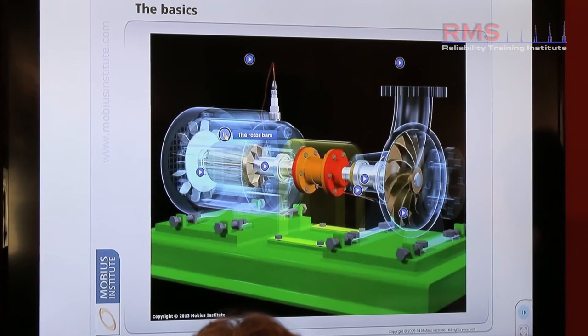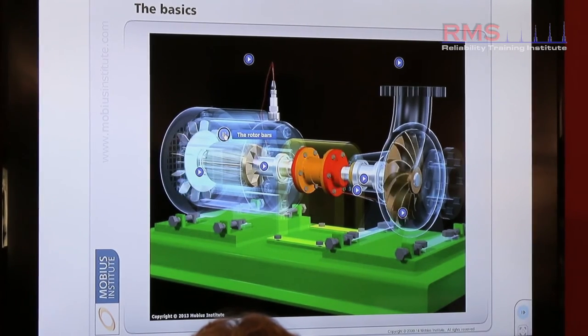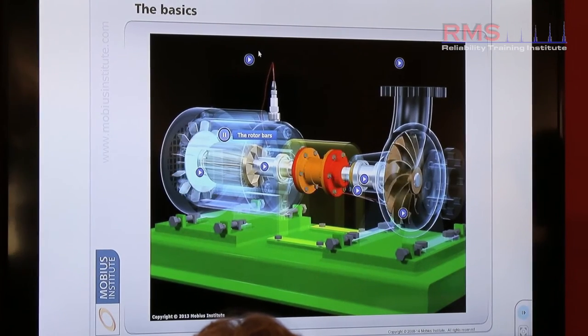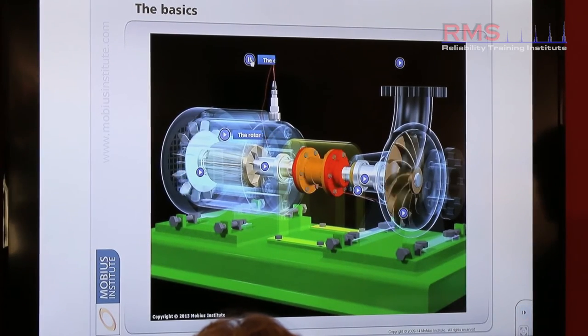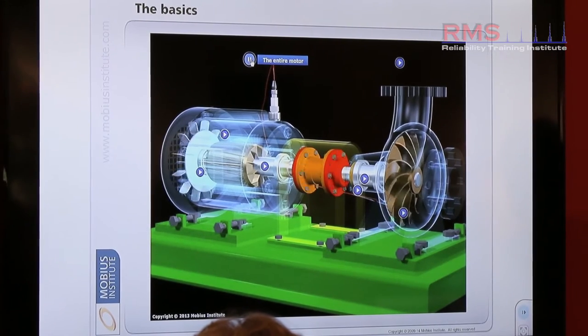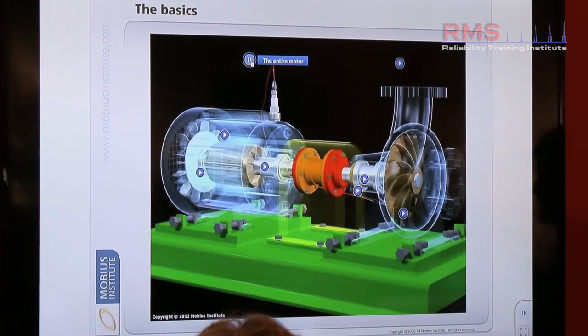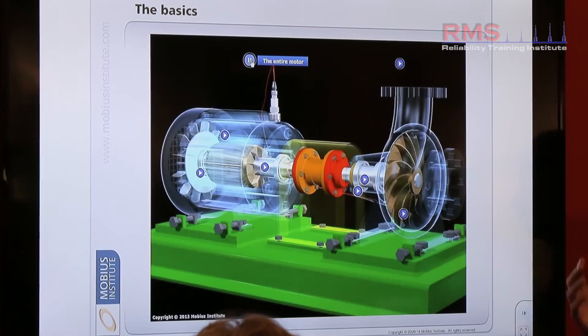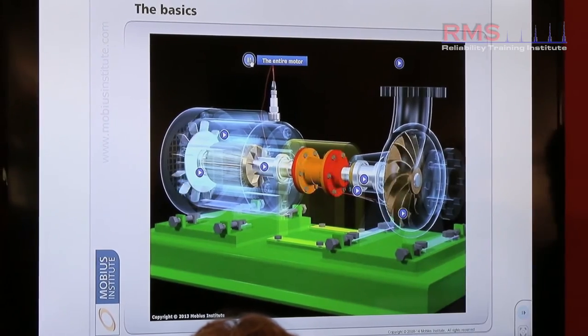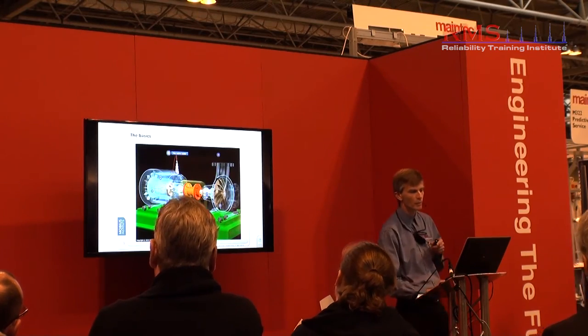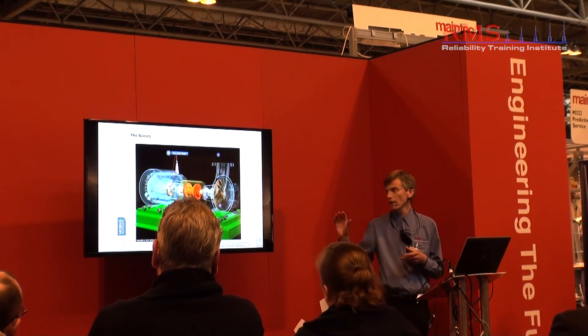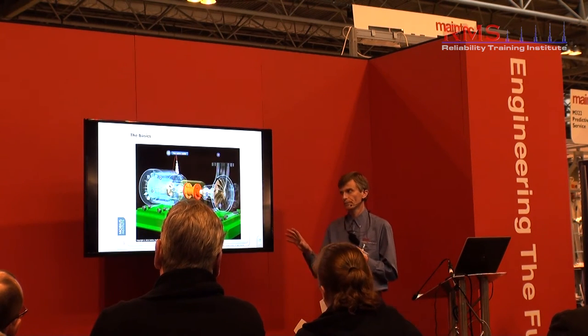Maybe the rotor bars have got a different heartbeat. Bringing them all together, it kind of gets a bit more complicated. But obviously the heartbeats combined together — we measure these heartbeats distinctly with our vibration sensor at key strategic measurement locations. And we can trend and track each component within the machine.